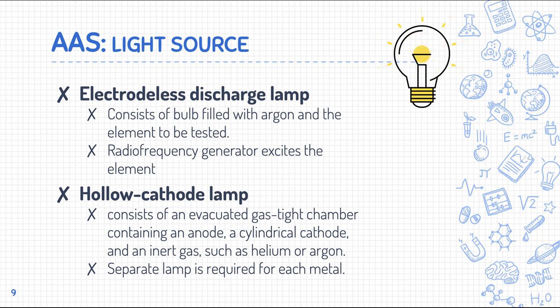The hollow cathode lamp consists of an evacuated gas-tight chamber containing an anode, a cylindrical cathode, and an inert gas — usually argon or helium. It requires a separate lamp for each metal. So if you are measuring aluminum, a different lamp is required; the same for copper, zinc, and so forth.